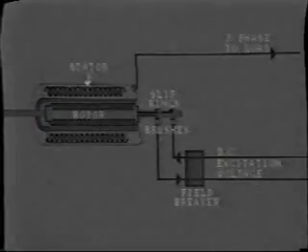Normally, protection relays are installed to detect reduction or loss of excitation. These relays may be used for alarm purposes, but more often they initiate tripping of the unit. Earlier loss of field relays worked by measuring current in the excitation circuit. When this fell below a preset level, the relay operated after a time delay. Nowadays, loss of field is detected by measurement on the generator high voltage side. One method is to use a megavar meter set to operate when the imported, that is, negative megavars reach a high level, implying that the unit is operating as an induction generator.